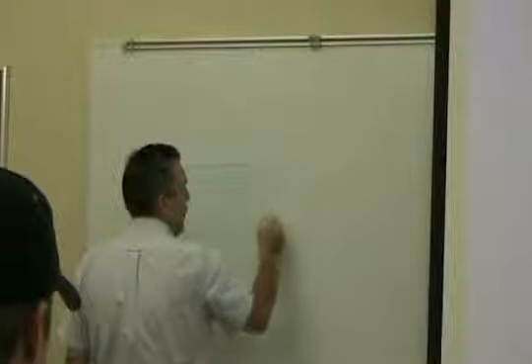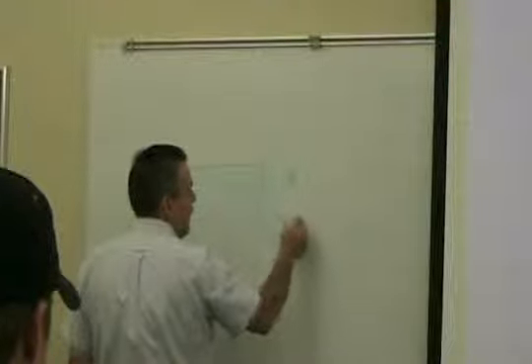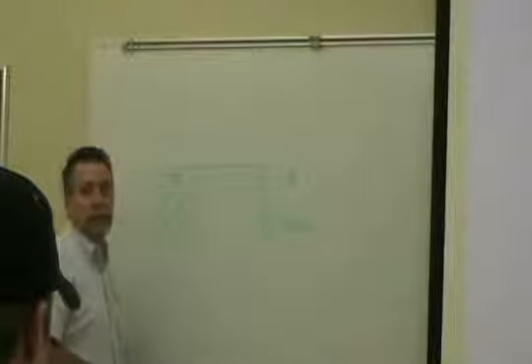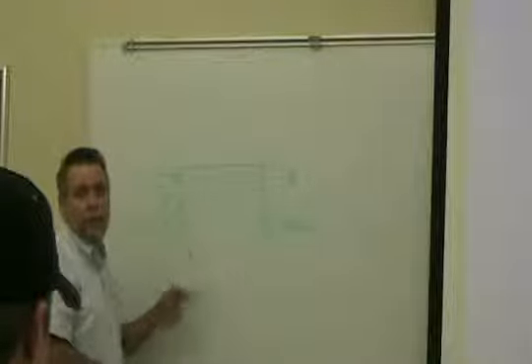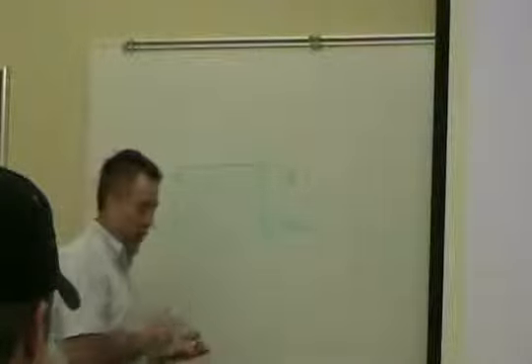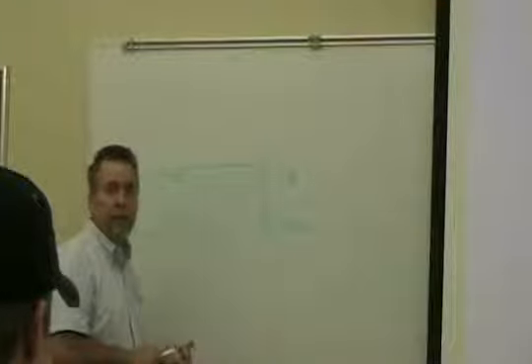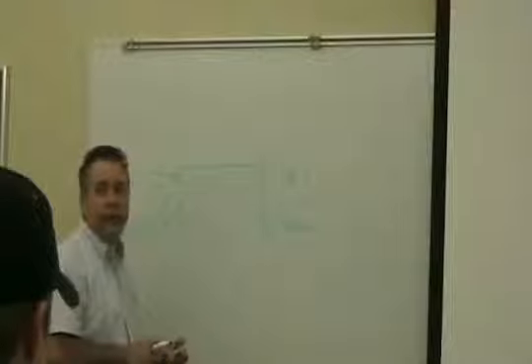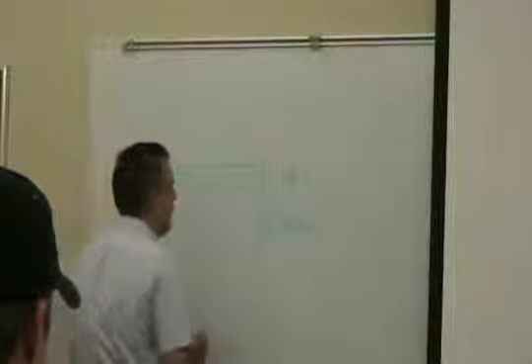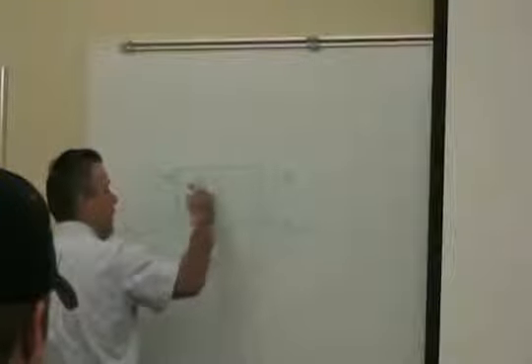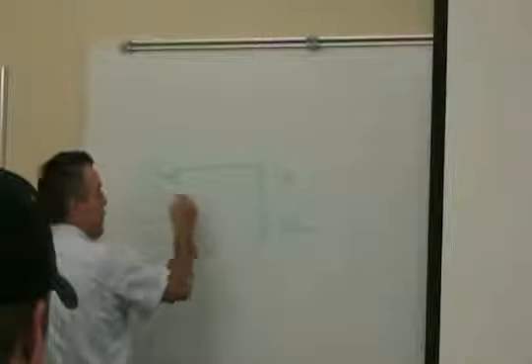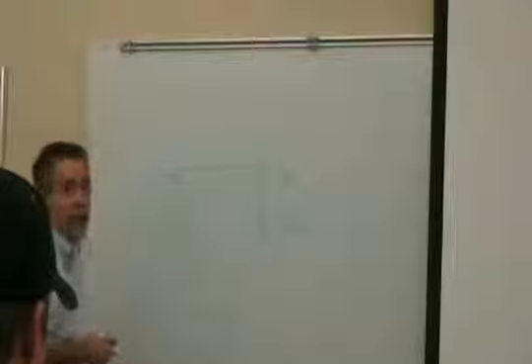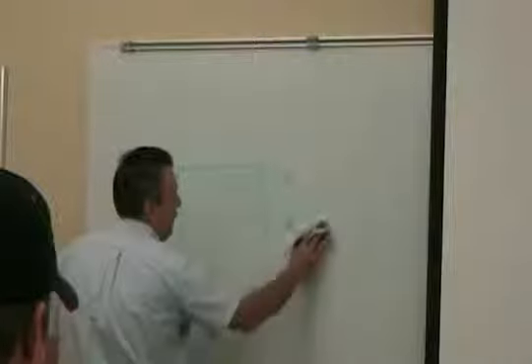So there's my return water going in, or my supply water coming out, and my return water going in. I've got to add glycol to this system because this is sitting outside. Whenever I add glycol, that increases my pump energy, decreases my heat transfer on my coils, and reduces your energy efficiency just a little bit. But in a fluid cooler, where I've just got this steel or copper heat exchanger with air going across it, that's one way of getting heat rejection out.